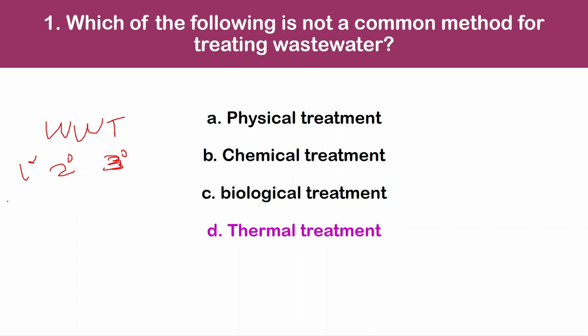When you have municipal wastewater flowing into a treatment plant, you will be able to see many suspended particles in it. Suspended in the sense you can see things like plastic papers or plastic covers, even floating in it. So right from that to other smaller easily separable solids, you have to be able to separate all of them out first itself. Otherwise it will be a big hindrance for the other two processes. So in the primary stage, you go for separating easily separable solids.